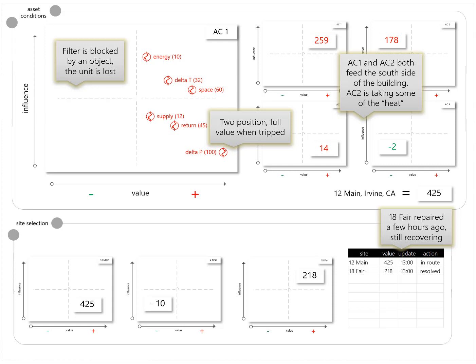We see that our supply temperature is rising. Our return is rising greater than that away from set point. Of course, I'm working from the bottom up in the upper left-hand corner. The space temperature is getting there. Our delta T is creeping up, and we're not using a ton of energy over the value, mostly because we've constrained the fan, but we're trying like the dickens to get this space cooled down.